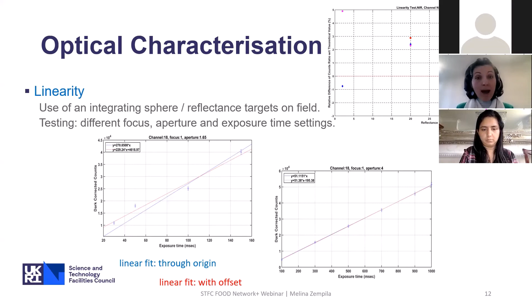Like, for example, if you have a radiance calibration certificate at specific settings and for some reason you have to change the exposure time because your target is getting too bright or too dark, then you may apply your certificate and account for this change through your linearity factors. So my point here is that there is always a way to move forward with this kind of issues.